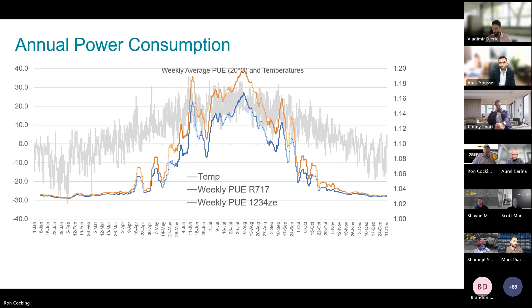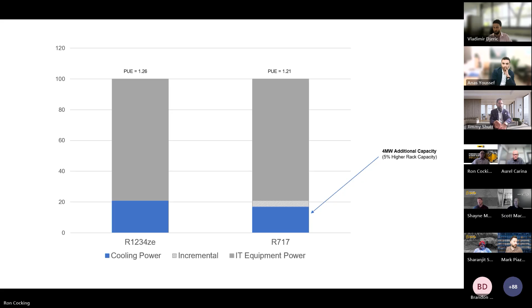What does this mean to us in the real world? Well, beyond the obvious energy reduction and reduced energy bills, as we've heard, energy availability is a problem in this industry right now. We get into situations where we're locked into a maximum amount of power available. In this example, we're showing a 100 megawatt site, one with R1234ZE, one with R717. It provides the ability to take that unused energy for cooling and apply it to what we're there to do. So in this application we can apply approximately 4 megawatts more to IT compute that in other scenarios we'd have to apply to cooling. Next slide.